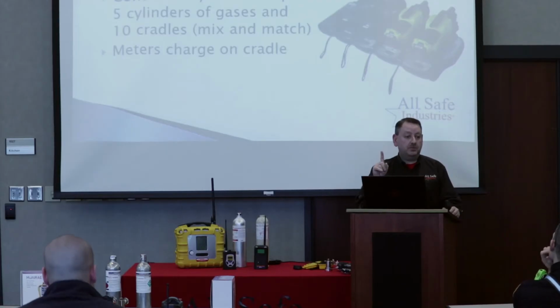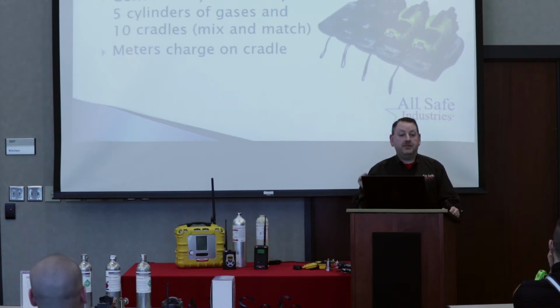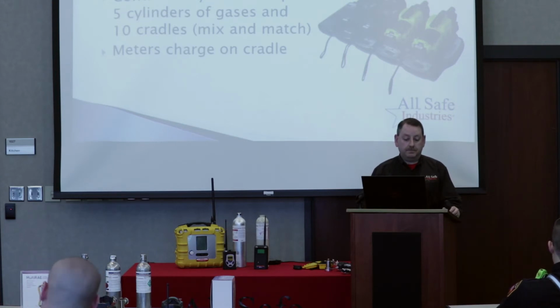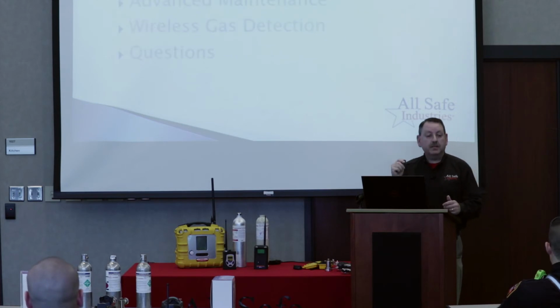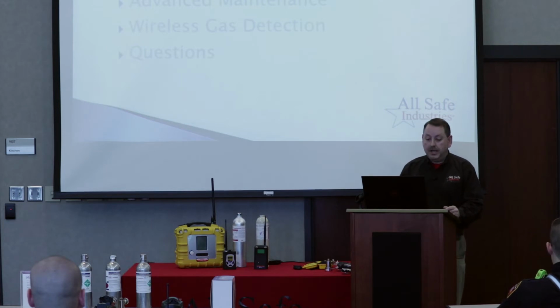But that's more than enough for what we're doing for you guys. Of course, you only have the 1 cylinder for the single gas meters. And then your MultiRAEs are a 2-cylinder calibration. So a cradle only is fine for that configuration. If you had a MultiRAE that had multiple sensors and you needed 2 or more cylinders, you would bump up to the AutoRae 2 system, and we can go up to 5 different cylinders of gas on an AutoRae 2 system. Okay? And again, the meters can charge on the cradle. So if you see fit, you could have the meter living on the cradle so it's always on charge. I've also seen some departments that just mount the cradles right to the bulkhead in your rig. That way it's always there, always ready to go. Okay? All right, that's the overview.